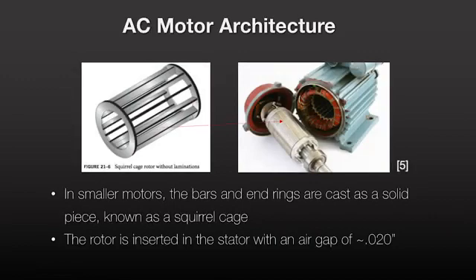Aluminum or copper conductors are embedded in the surface of the cylinder. The rotor is inserted in the stator with an air gap of roughly 20 thousandths of an inch, which is half a millimeter. Any more of an air gap will significantly reduce the ability of the stator to induce current flow in the rotor.